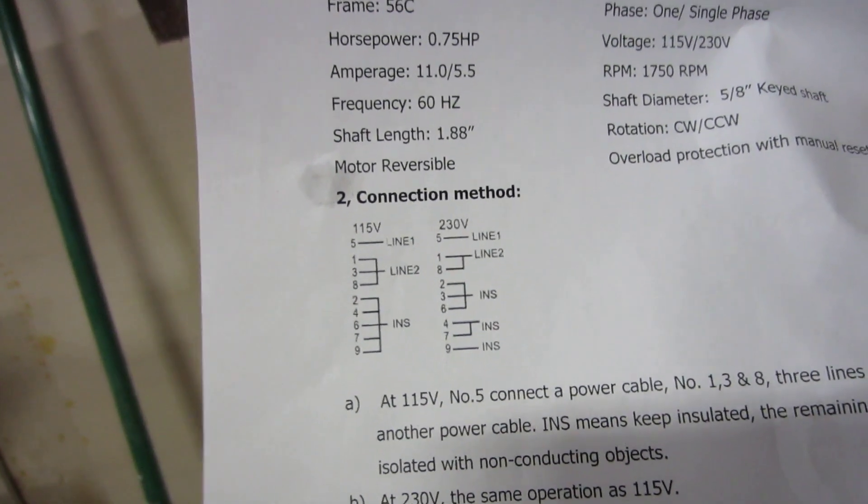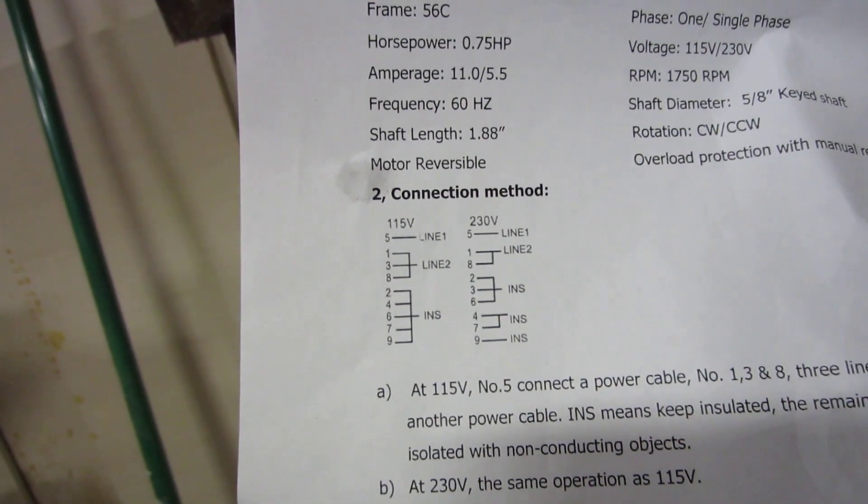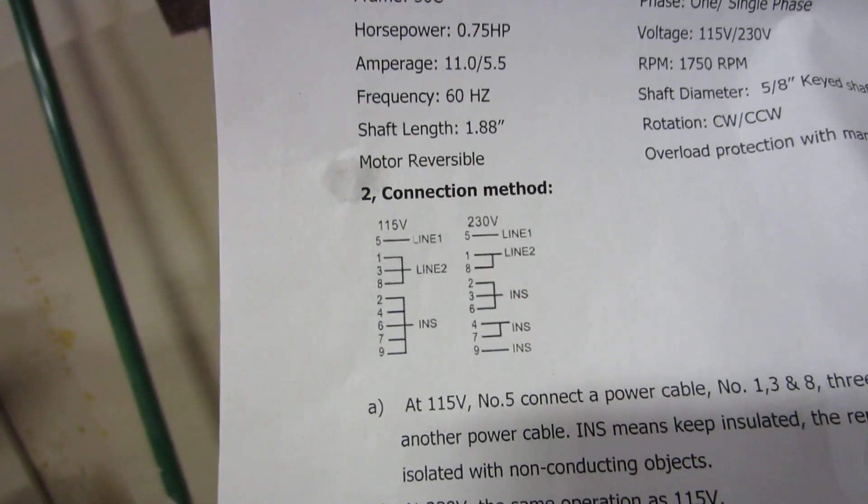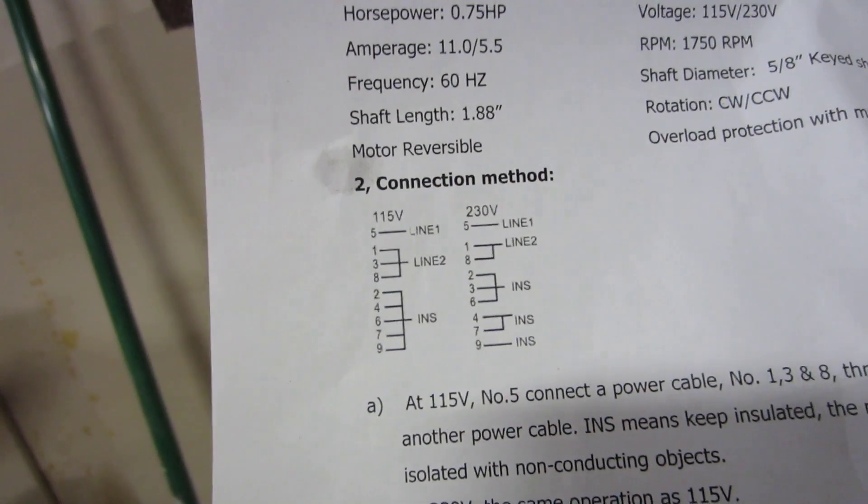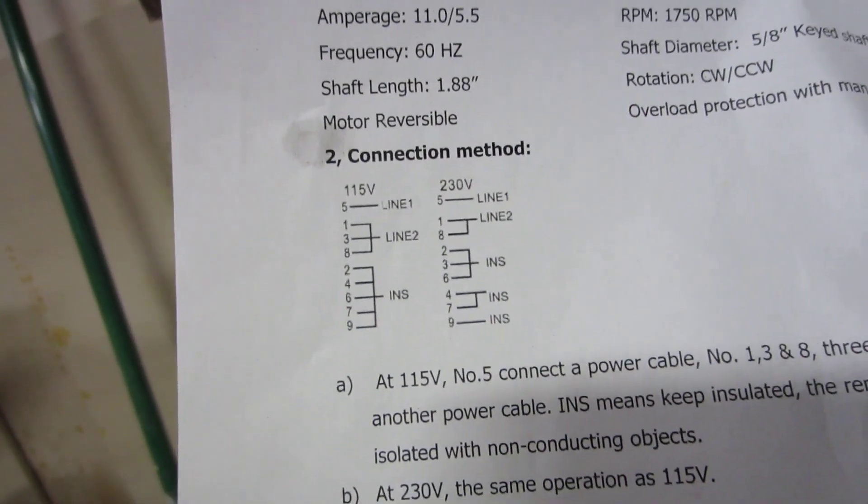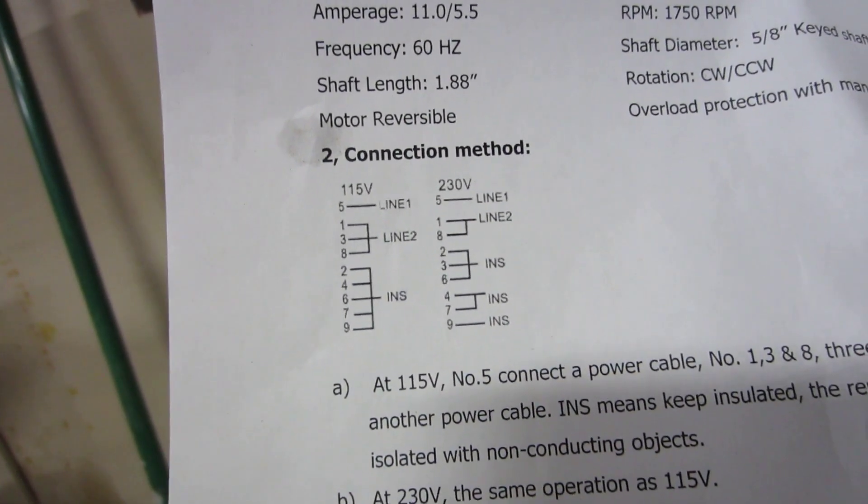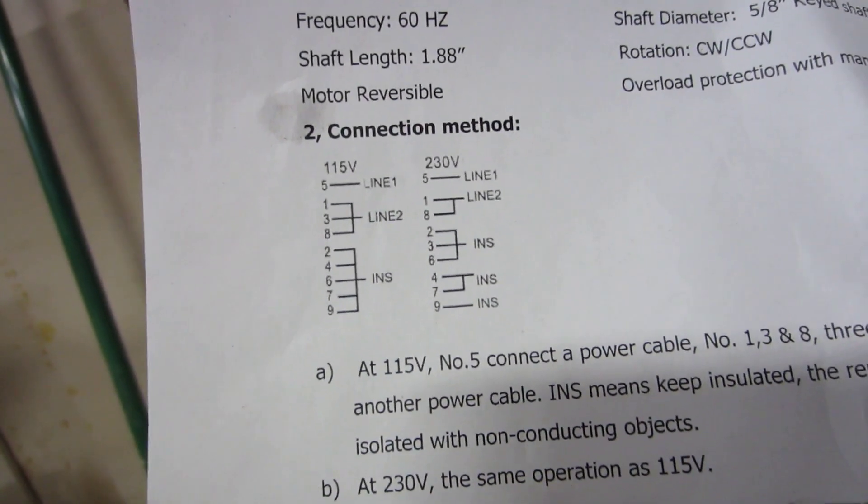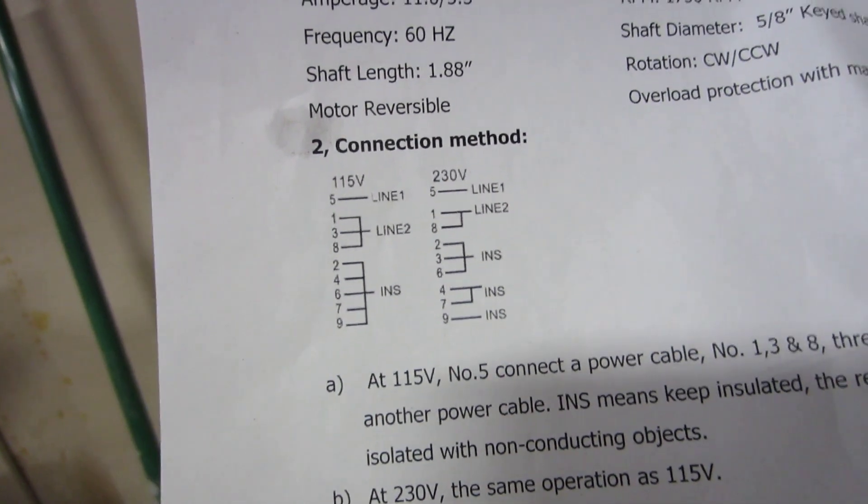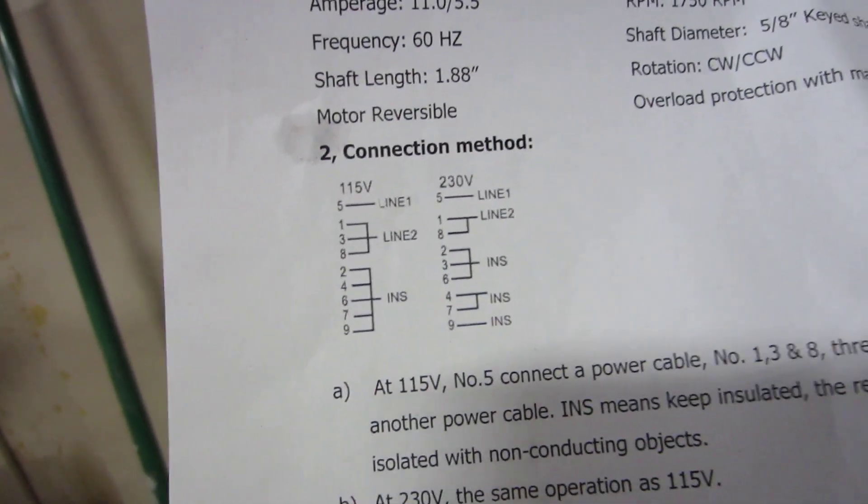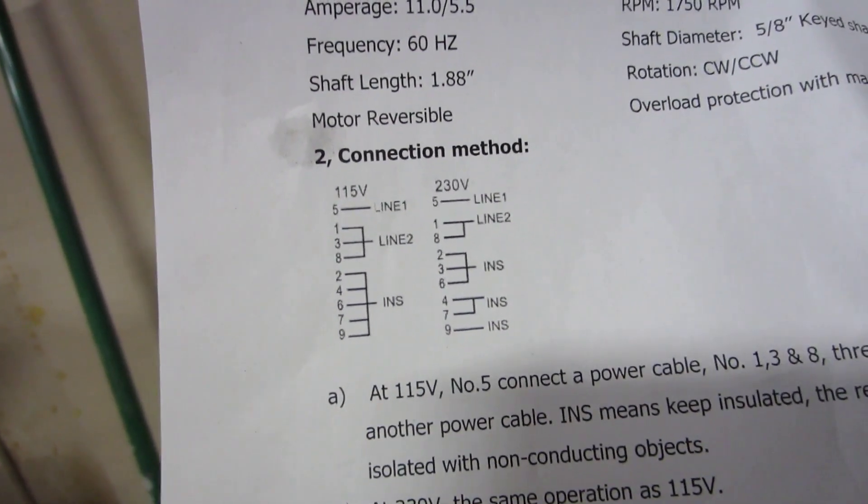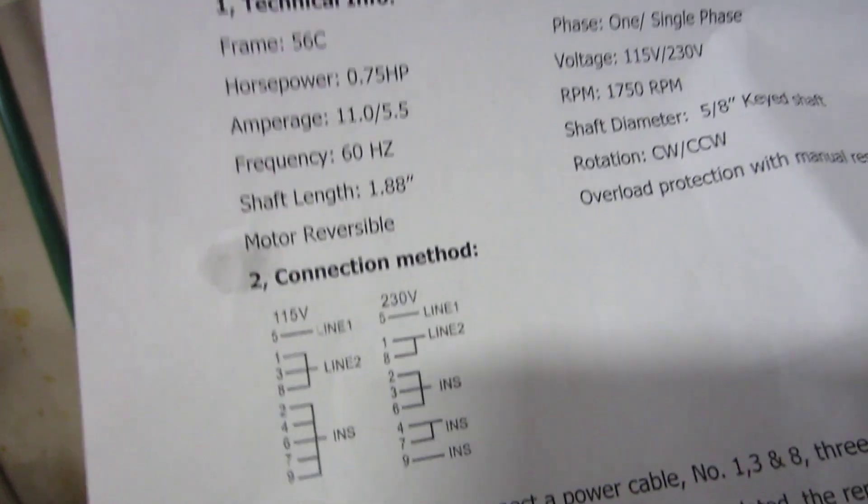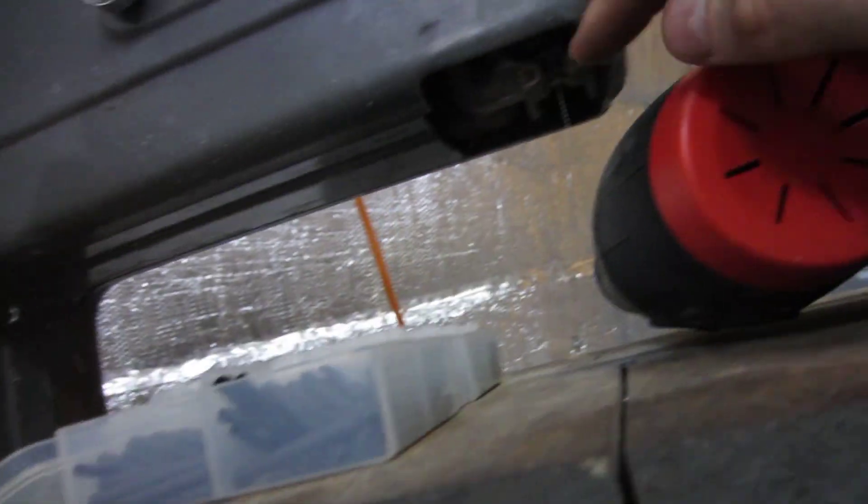You can see here they have line 5 goes to the hot in this case, line 2 goes to the neutral, and then INS is the insulation, it just means it doesn't go to anything but the wires are grouped together. That's for the 115 versus the 230. Doing it in that configuration is clockwise, so this spins the right direction.